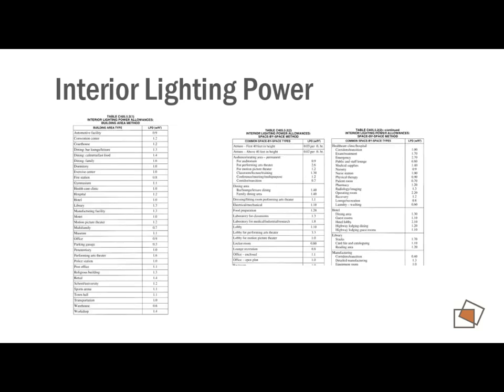These power density tables are something that we have to comply with, so this is interior lighting power. This is something we're complying with here in Springfield. There are two methods to calculate it. Either you can look at your building as a whole, find your office building and add up all the square footage and all the wattage, and if you come in at 0.9 watts per square foot, you're good to go. Or you can do an interior method where you look at each individual space, add up those square footages, and look at all the allowances. If you meet them, you're good to go. We found these to not be that hard to meet, to be honest, especially the 2012 values. They've gotten a little more aggressive in more recent code updates, but with the way that LED lights perform, this generally isn't an issue unless you're really doing something crazy.